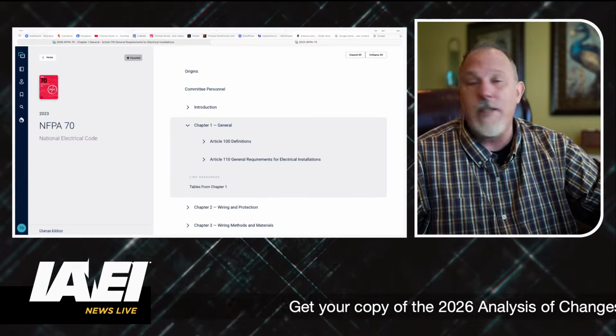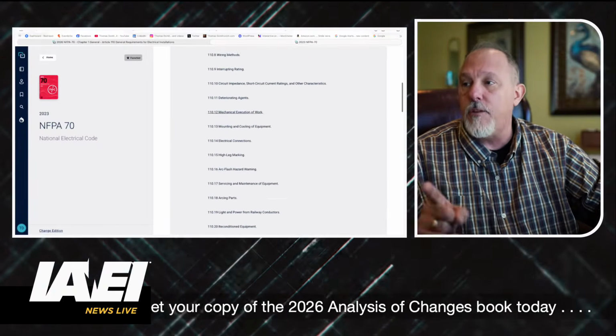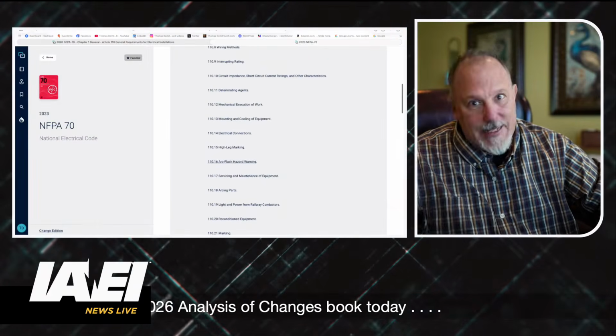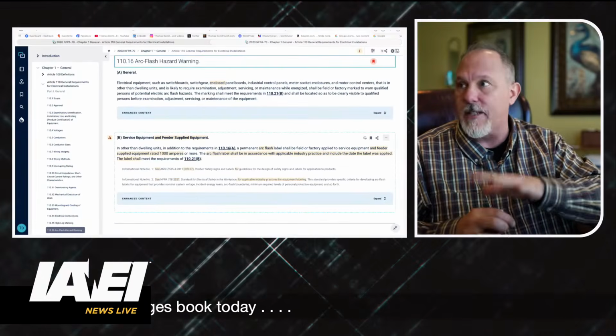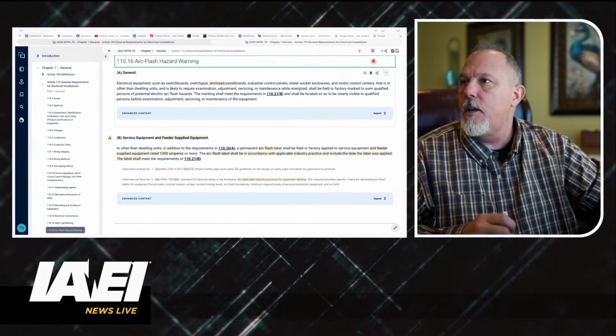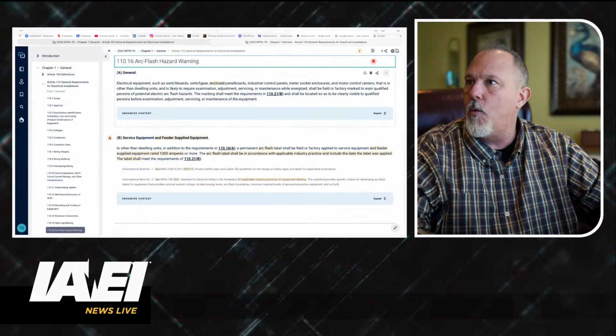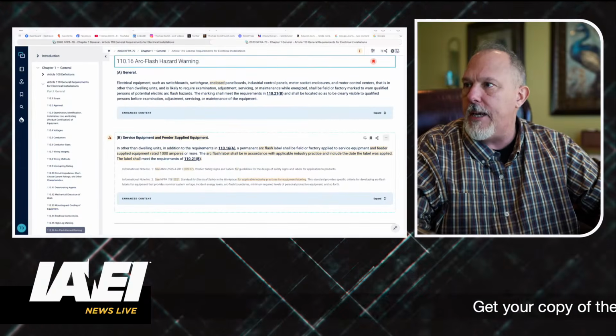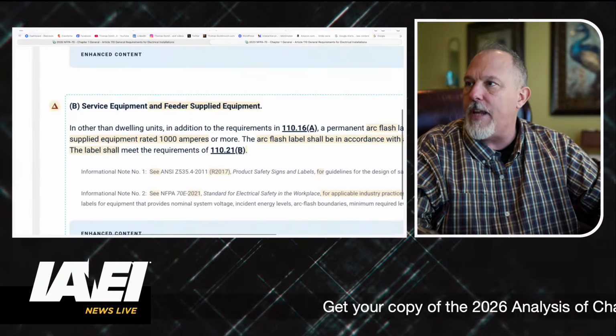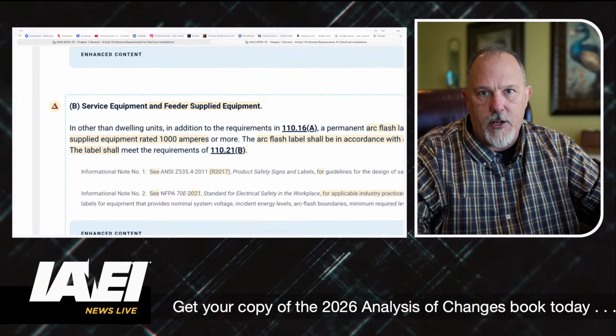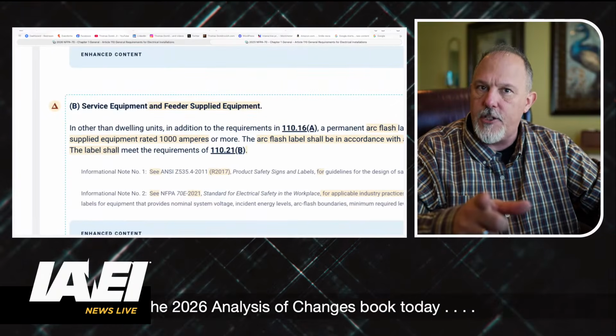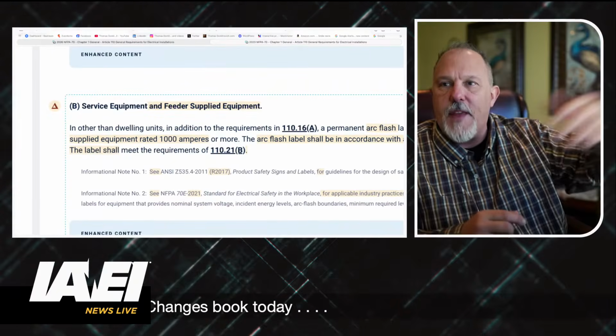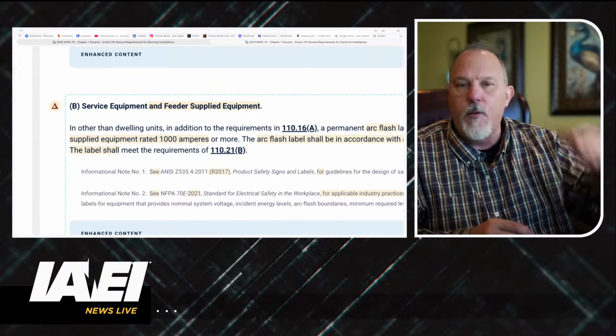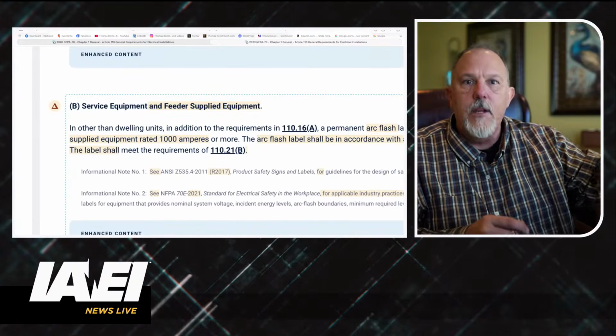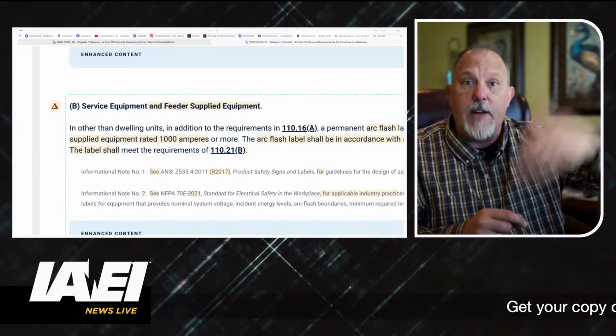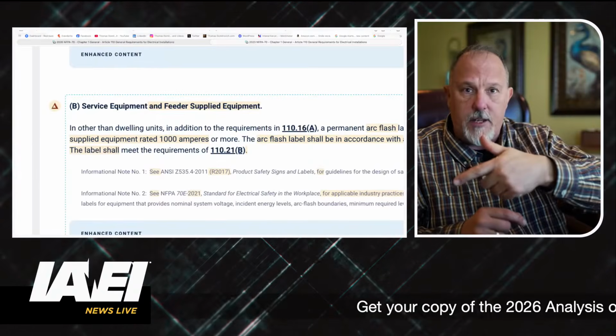110.16. Okay, so 110.16 used to focus on... now last cycle, we made a change last cycle. What we did in B was we added this, and feeder supplied equipment. That was a big change, because then we picked up 1,000 amp feeder supplied equipment. So you have service equipment, 1,000 amps and above, that had to have an arc flash label.